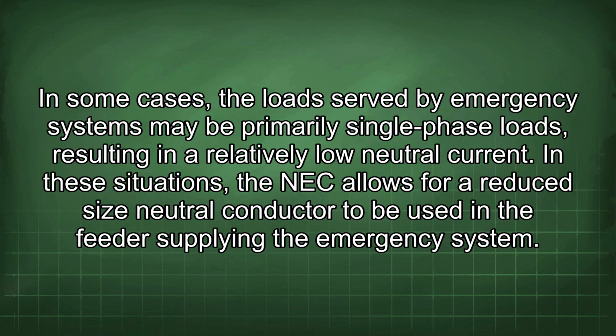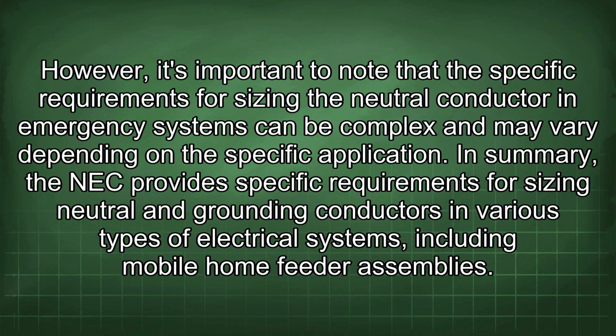In some cases, the loads served by emergency systems may be primarily single-phase loads, resulting in a relatively low neutral current. In these situations, the NEC allows for a reduced-size neutral conductor to be used in the feeder supplying the emergency system. However, it's important to note that the specific requirements for sizing the neutral conductor in emergency systems can be complex and may vary depending on the specific application.